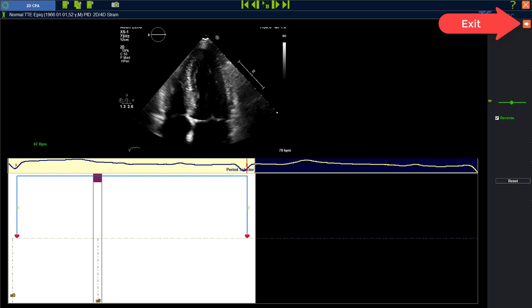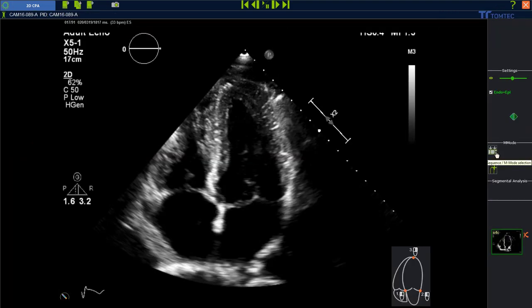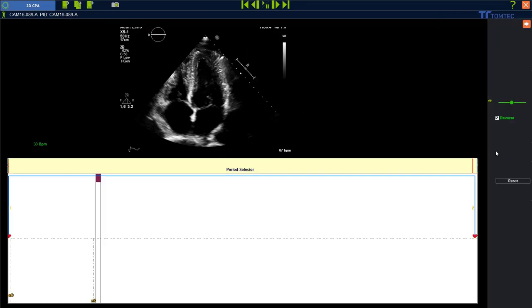Leave the menu from the upper right corner. Now, a second example: in this case you can see we have no ECG information transferred from the machine as DICOM information, so we have to set the ECG manually.